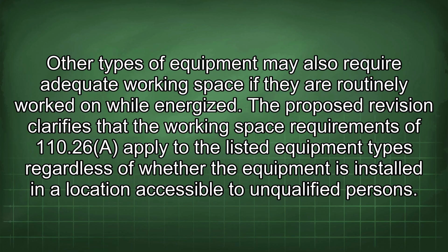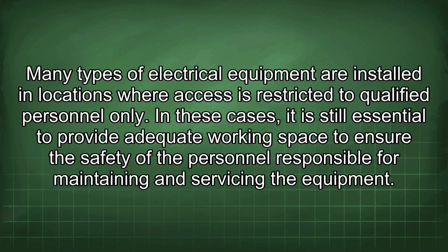The proposed revision clarifies that the working space requirements of 110.26 apply to the listed equipment types regardless of whether the equipment is installed in a location accessible to unqualified persons. Many types of electrical equipment are installed in locations where access is restricted to qualified personnel only. In these cases, it is still essential to provide adequate working space to ensure the safety of the personnel responsible for maintaining and servicing the equipment.